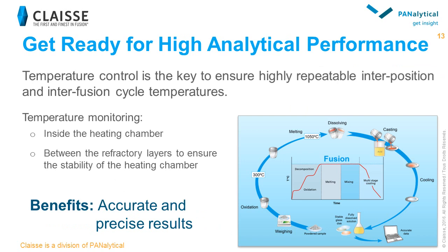To ensure that the glass disks and solutions prepared with the Deox Advanced generate accurate and precise results, temperature control is key. This new version is equipped with two thermocouples: the first is located inside the heating chamber and the second is located between the refractory layers of the chamber. The second thermocouple gives information about the stability of the heating chamber. Also, the temperature inside the heating chamber is continuously displayed on the touch screen control panel.